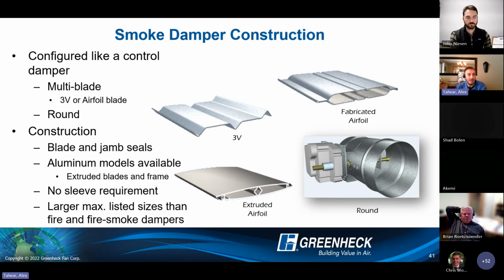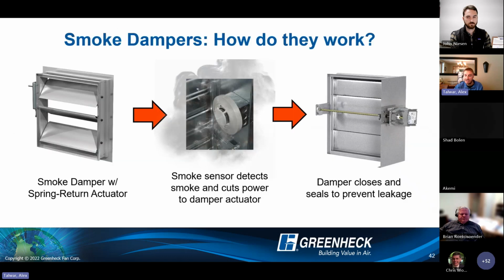So we do have the aluminum style products available, and to help us pass these leakage tests, we will use blade and jamb seals. So some type of silicone seal usually along the blade edge to seal up blade to blade. And then it's a springy stainless steel type of jamb seal, we call it, along the edge of the damper frame to seal up against the frame and the edge of the blade. And then in terms of smoke dampers, we are able to build them much larger than fire and fire smoke just due to the nature of the testing and things like that. So not quite as many size restrictions there.